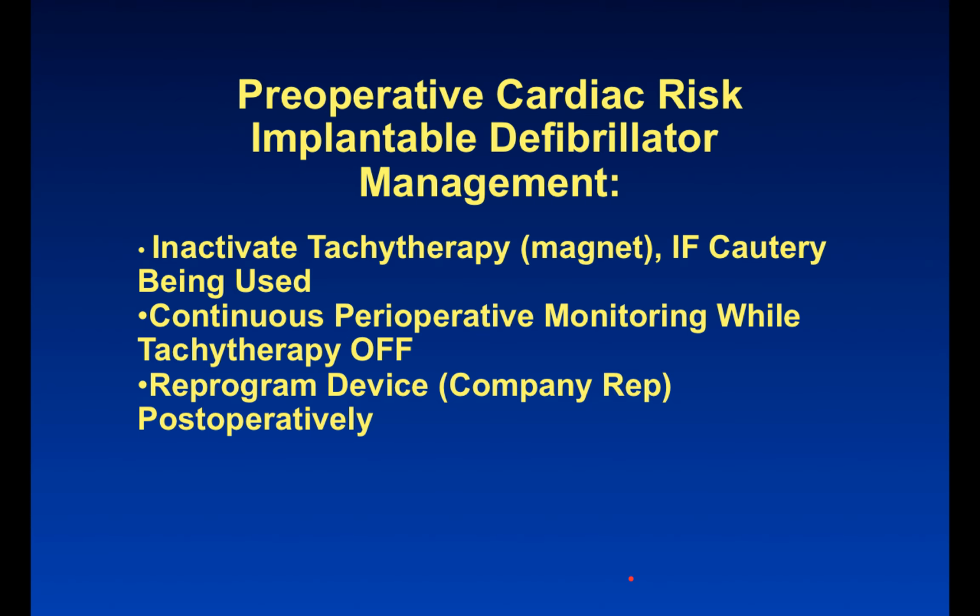And then the device has to be reprogrammed. Typically, we contact the company rep who comes in postoperatively and make sure that the device is back to its original programming.